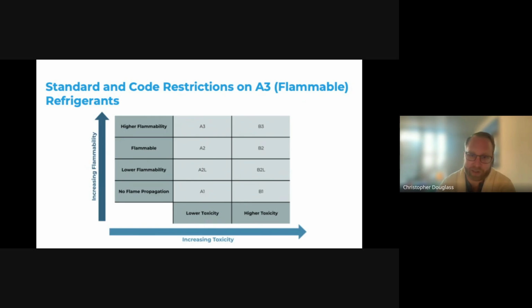Refrigerants are assessed for their flammability and toxicity based on a scale, where the numbers increase as the flammability increases, and A versus B denotes whether the refrigerant is toxic, like ammonia, for example. In the US, the two main standards bodies with regard to AC heat pumps and refrigeration equipment are UL, which sets the requirements for equipment design and construction, and ASHRAE, which broadly speaking covers the equipment installation requirements.